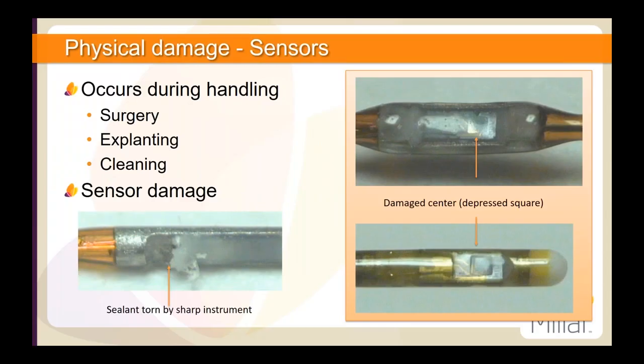During handling of the catheters, care must be taken not to damage the sensor window. Fingers, forceps, and any other instruments must be kept away from this area. Direct pressure to the sensor window may cause the sensor diaphragm to fail, as is shown in the photos to the right here. This depressed square in each of these photos is where the sensor has been pressed in by direct pressure. The photo on the left here shows damage to the sensor sealant. This has been caused by it being pierced with a sharp instrument.